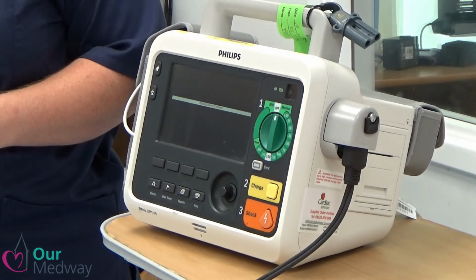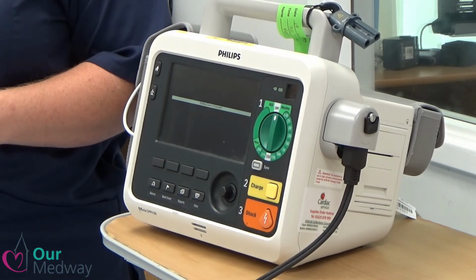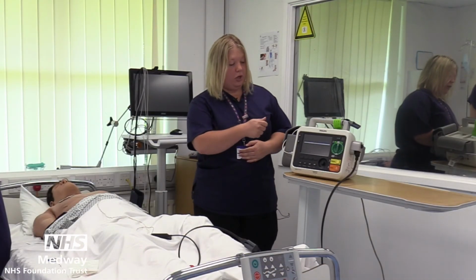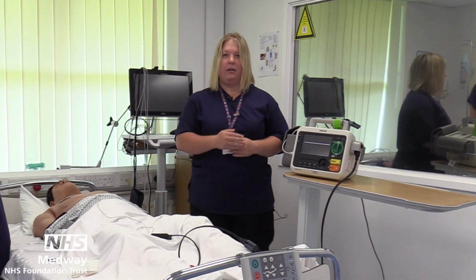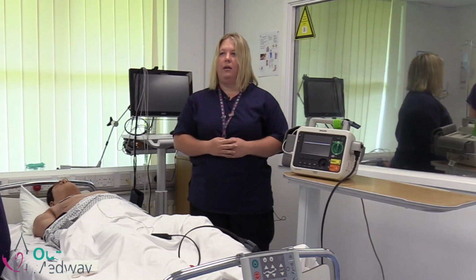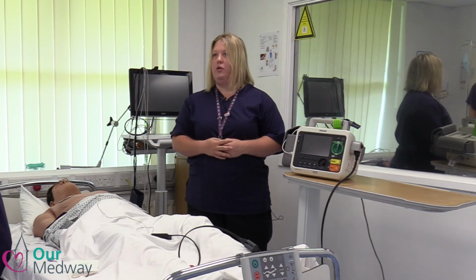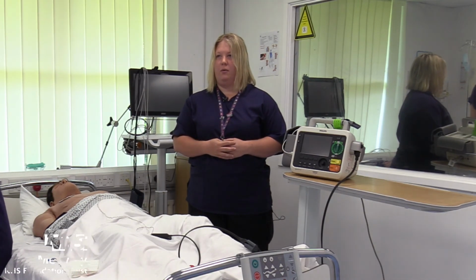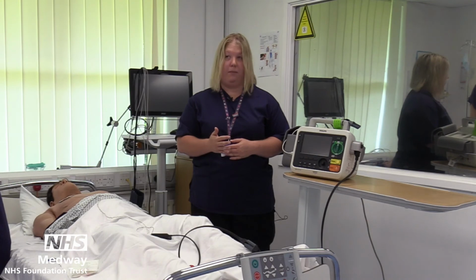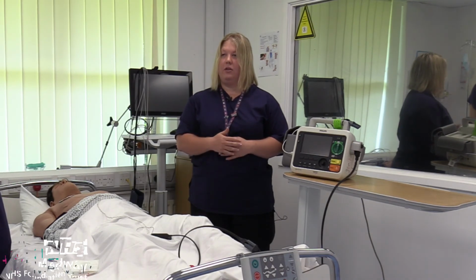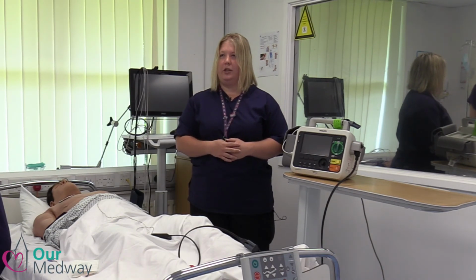And then turn the defibrillator off. It takes about 10 seconds to shut down. If you turn it back on within that shutdown period, the defib will remember that patient that it was just being used on, and your data will still be available. After that 10-second period, all that data will be lost and the machine will be ready for a new patient or new scenario.